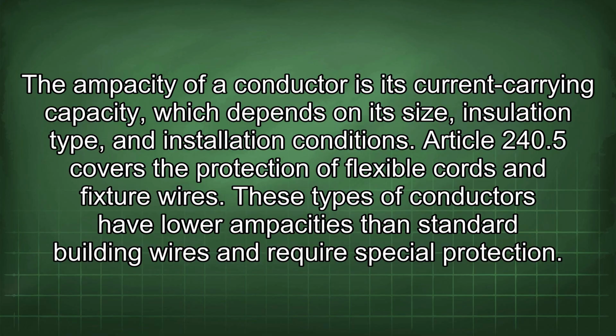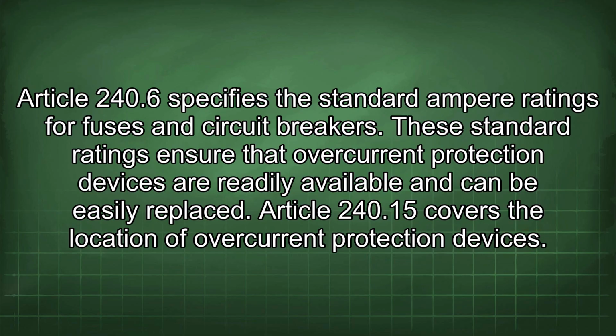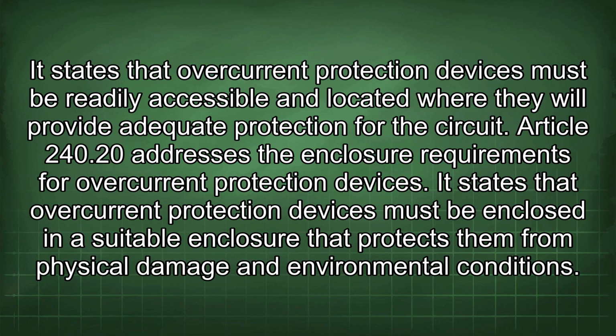Article 240.5 covers the protection of flexible cords and fixture wires. These types of conductors have lower ampacities than standard building wires and require special protection. Article 240.6 specifies the standard ampere ratings for fuses and circuit breakers. These standard ratings ensure that overcurrent protection devices are readily available and can be easily replaced. Article 240.15 covers the location of overcurrent protection devices. It states that overcurrent protection devices must be readily accessible and located where they will provide adequate protection for the circuit.